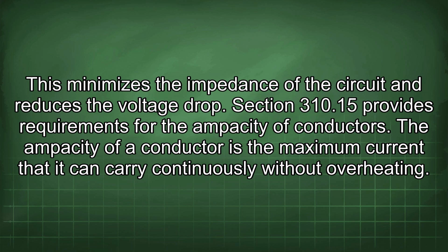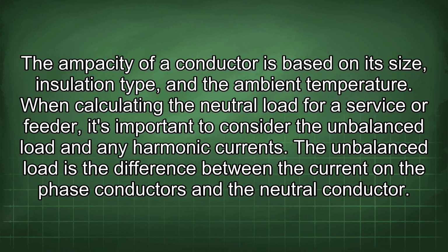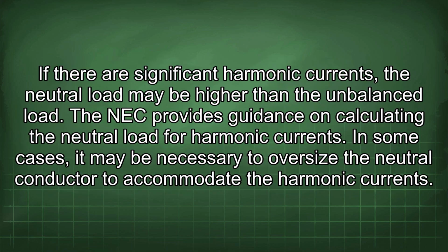Section 300.3(B) requires that all conductors of a circuit, including the neutral conductor, be installed together in the same raceway or cable. This minimizes the impedance of the circuit and reduces the voltage drop. Section 310.15 provides requirements for the ampacity of conductors. The ampacity of a conductor is the maximum current that it can carry continuously without overheating. The ampacity of a conductor is based on its size, insulation type, and the ambient temperature.